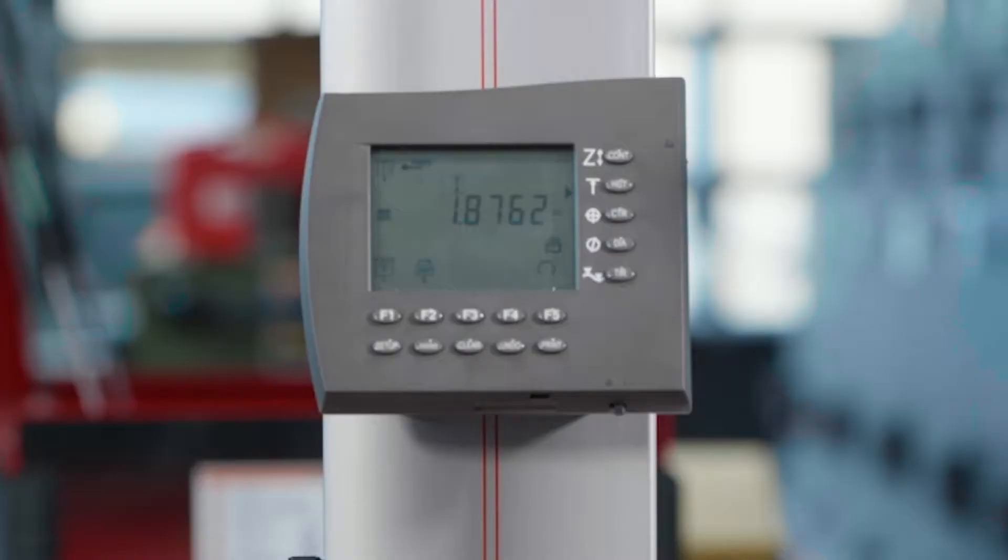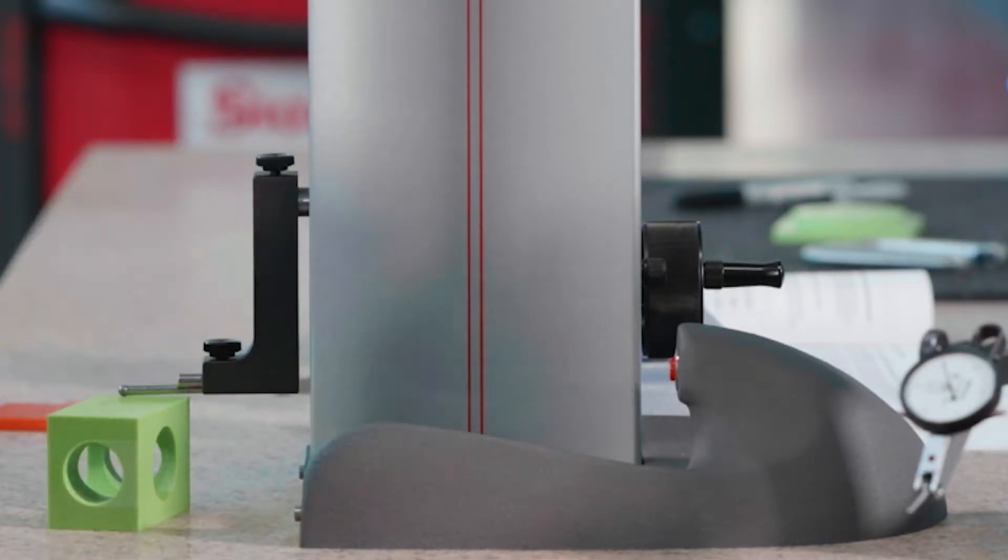If I press this red button on the side of the machine, it'll tell me the difference between those two points. This also has a total indicator reading function, which is really handy. It's good for quick measurements to see if two points are different and by how much.